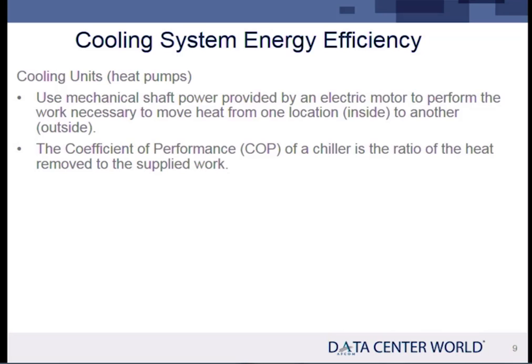Now, you'll see chiller efficiencies in documentation listed kind of funny. They go kilowatts per ton. I love this thing, kilowatts per ton. Oh, can't you give me the same units? Right, because you convert a ton to a kilowatt. It's a ratio about 3.541, something terrible, right, that you can convert it. And then it's kilowatts per kilowatts, and that is the coefficient of performance. And generally, as I said, on a good day, they run about 4.